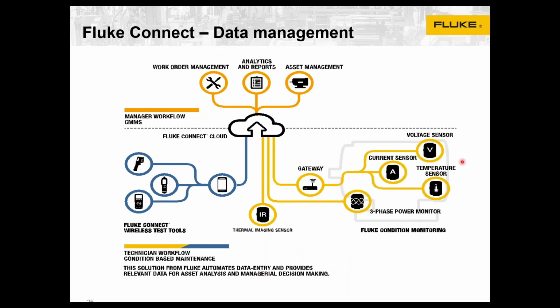A little bit deeper look at that. There may be some condition monitoring type of tools, such as the vibration sensors, streaming data on assets with alarms into the cloud. Here's an example of the 3 different types of route-based thermal, vibration, electrical measurements. All can be fed into the Fluke cloud, assigned to assets. You can generate work orders if you want to, or if you don't need to start that big, then just literally use the handheld tools and just take corrective actions based off of that. The platform allows you to grow as you need to grow, but doesn't force you to have to create a full CMMS system.